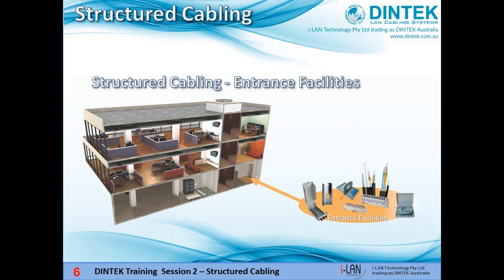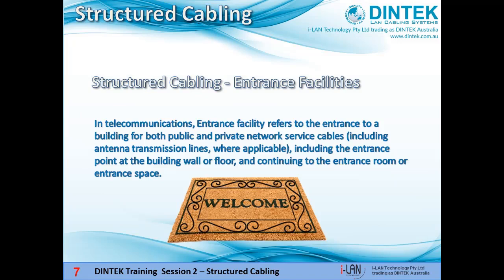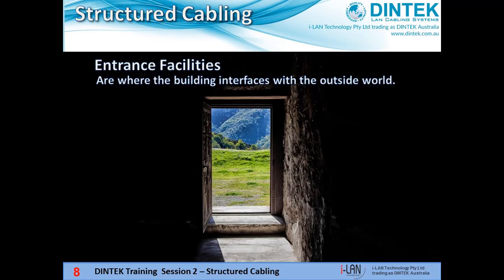In this webinar we'll be looking at the first step in the line — the entrance facilities, where our services first enter the building. So what are entrance facilities? In telecommunications, entrance facilities refers to the place in a building where all of the public and private cabling comes in. In a large building that'll usually mean a room in a basement somewhere; in a small building it could be just an enclosure on the outside wall. Put simply, entrance facilities are where the building interfaces with the outside world.